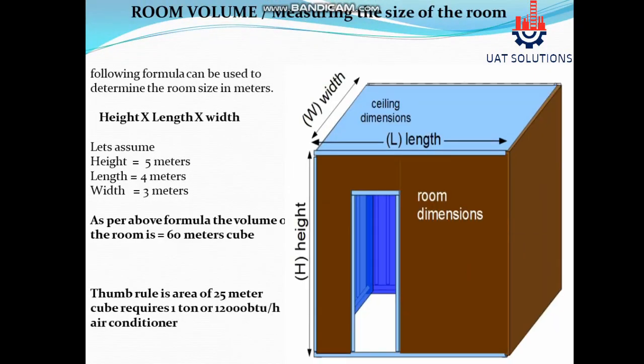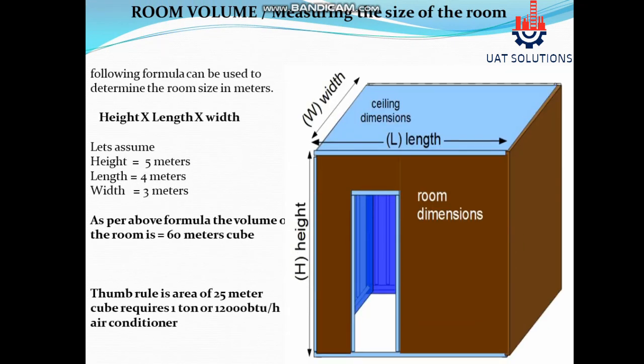Room volume — measuring the size of the room. The following formula can be used to determine the room size in cubic meters: height × length × width. Assuming height is 5 meters, length is 4 meters, and width is 3 meters, the volume equals 60 cubic meters. The thumb rule is that 25 cubic meters requires 1 ton or 12,000 BTU/h air conditioner.